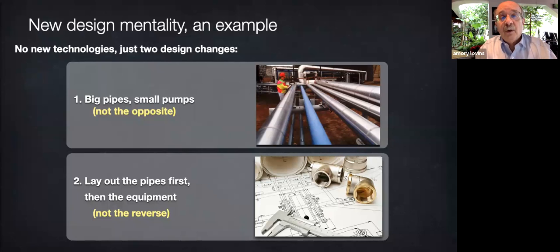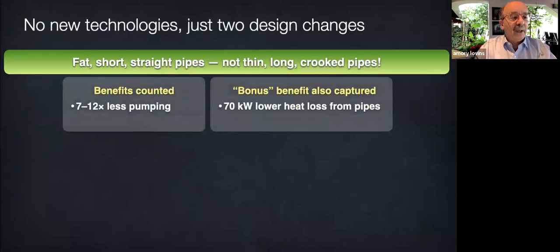So we should design out friction by using fat, short, straight pipes rather than thin, long, crooked pipes. And if your retrofit also cuts flow through the same pipe, this effectively oversizes the pipe, cutting friction as nearly the fifth power of diameter, and energy use will fall as roughly friction times the cube of flow. In a Dutch industrial case, this approach cut the pumping energy by at least 7-fold. Actually, the engineer told me he ultimately measured it at 12-fold with lower capital cost. As a free bonus, it also saved 70 kilowatts of heat loss with a 2-month payback because it was easier to insulate short straight pipes than long crooked pipes.